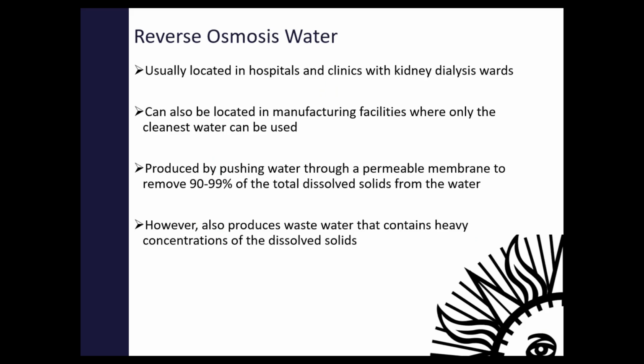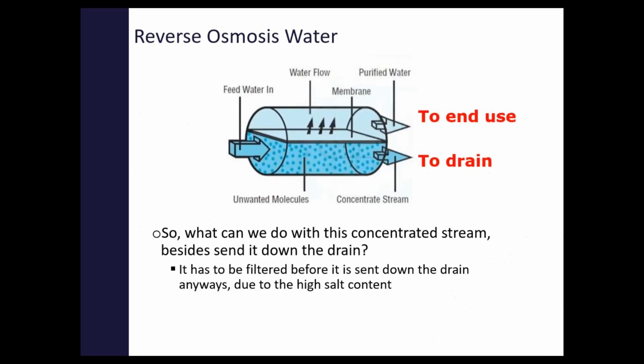Just make sure you measure and figure out what the ratio is of RO water to wastewater that's coming out of their RO system. If you pass the water through an RO system once, you're usually only taking maybe 20% of the water you pass in, depending on how much you filter out. 20 to 50% is what you're getting out as usable RO water, purified water, and then the rest you're sending down the drain as a concentrate stream.